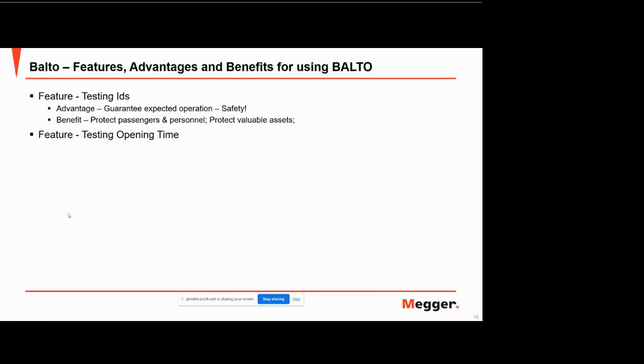The other feature for Balto is testing the opening time. So obviously, a DC high-speed circuit breaker is a mechanical and an electrical operation, but any mechanical device is subjected to wear and tear over the period of time that it's in service, and this could be up to 40 or 50 years. It'll start to degrade, it'll start to get residue and buildup of various elements in its lifetime. So we need to make sure that we can be confident that the opening time is maintained throughout its life cycle.